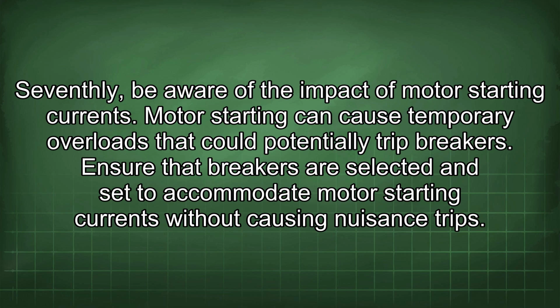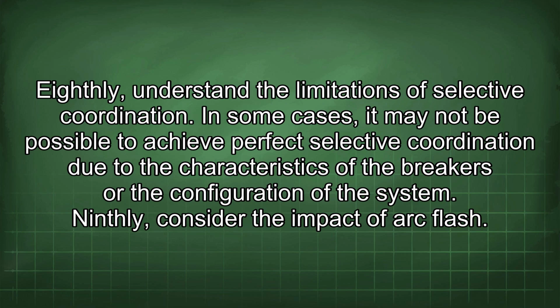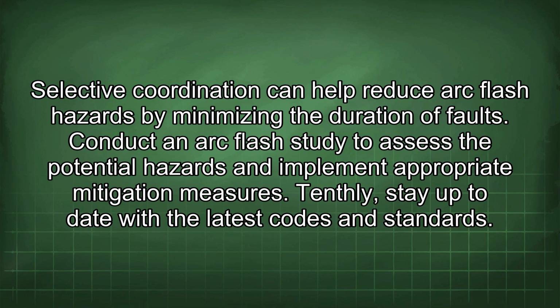Seventhly, be aware of the impact of motor starting currents. Motor starting can cause temporary overloads that could potentially trip breakers. Ensure that breakers are selected and set to accommodate motor starting currents without causing nuisance trips. Eighthly, understand the limitations of selective coordination. In some cases, it may not be possible to achieve perfect selective coordination due to the characteristics of the breakers or the configuration of the system. Ninthly, consider the impact of arc flash. Selective coordination can help reduce arc flash hazards by minimizing the duration of faults. Conduct an arc flash study to assess the potential hazards and implement appropriate mitigation measures.